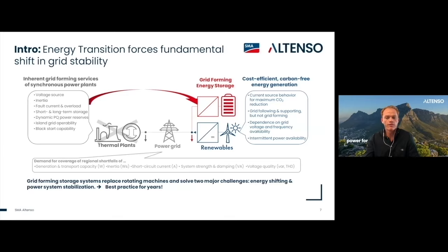So unlike your traditional grid following inverters, grid forming inverters behave more like a synchronous generator. They set the reference for voltage and frequency and are able to respond dynamically to changes in load and system conditions. So this is going to be of growing importance on the grid level, particularly as Eskom phases out its spinning reserves in South Africa. That's our coal-fired power plants, and adds more renewables. There's going to be inherently a lot of loss of inertia and system stability in the system. And so batteries and grid forming technology is a great way to address that.